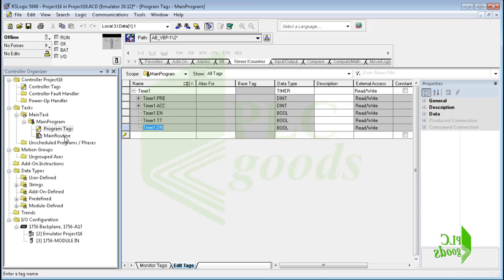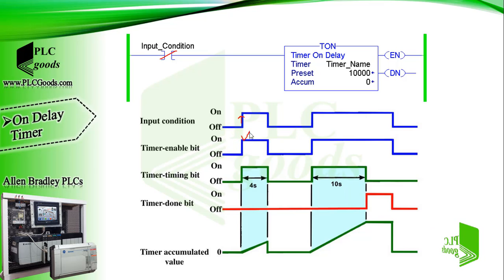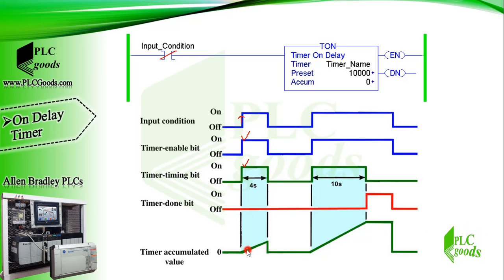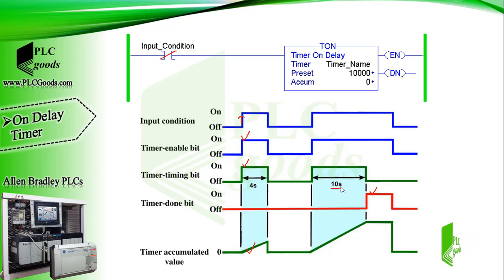The done bit signals the end of the timing process by changing states from false to true. This diagram shows how the on delay timer works: when the rung input logic is true, the enable bit is true, the timer starts its work, the timer timing bit is true, and the accumulated value starts incrementing based on milliseconds. When its value reaches the preset value, the timer done bit will change from 0 to 1.